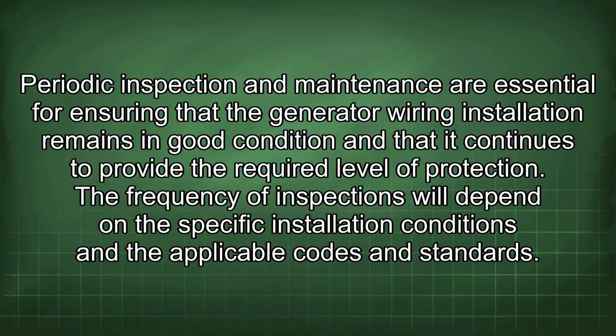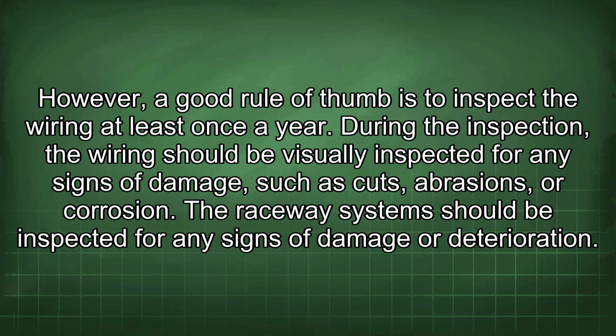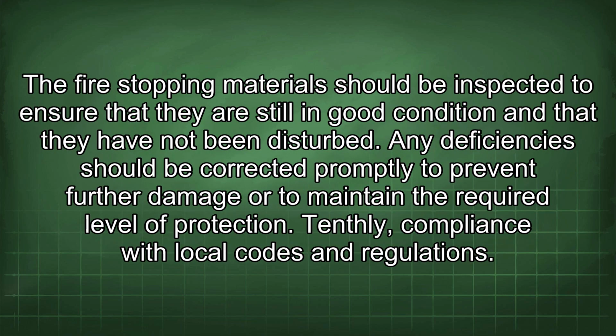Periodic inspection and maintenance are essential for ensuring that the generator wiring installation remains in good condition and that it continues to provide the required level of protection. The frequency of inspections will depend on the specific installation conditions and the applicable codes and standards. However, a good rule of thumb is to inspect the wiring at least once a year. During the inspection, the wiring should be visually inspected for any signs of damage, such as cuts, abrasions, or corrosion. The raceway systems should be inspected for any signs of damage or deterioration. The fire-stopping materials should be inspected to ensure that they are still in good condition and that they have not been disturbed. Any deficiencies should be corrected promptly to prevent further damage and to maintain the required level of protection.